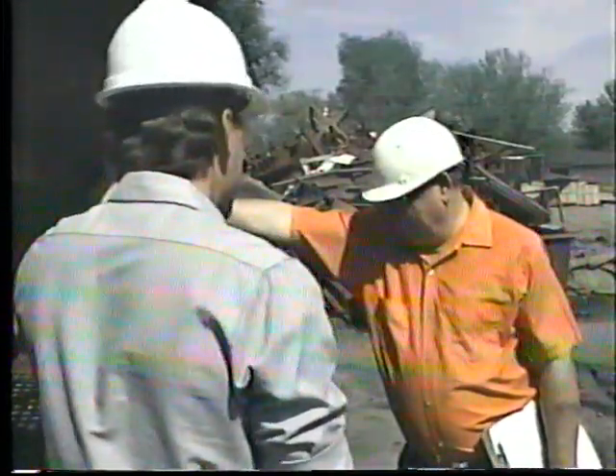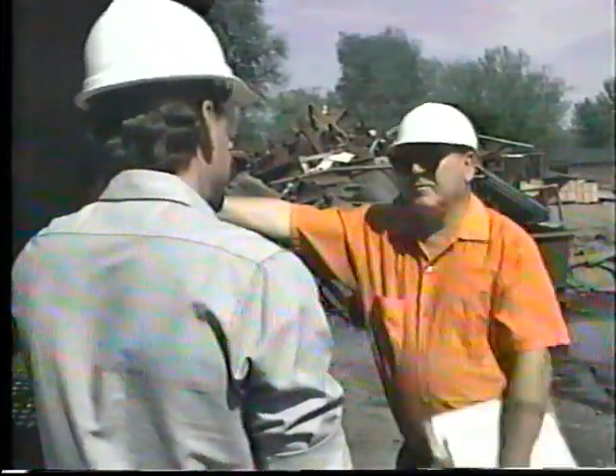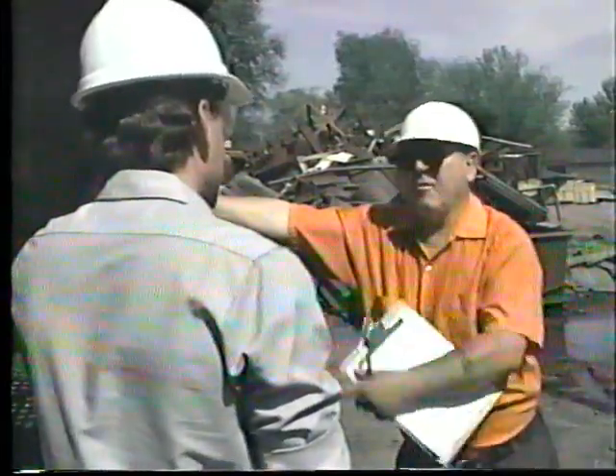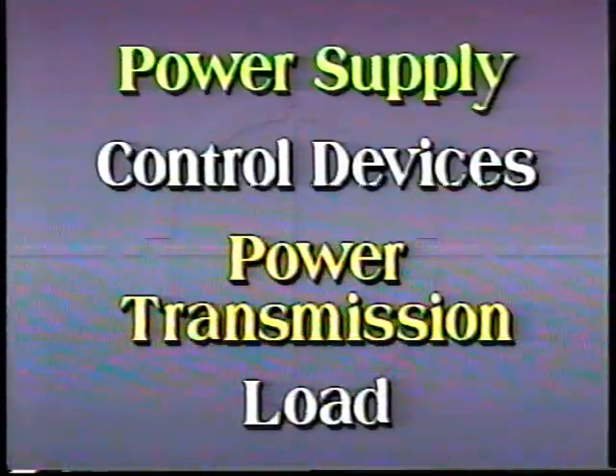It may also be a good idea to ask the operator about recent changes. This could be a process change, a raw materials change, or even a change of suppliers. Often, the operator is the best source of information about unusual machine behavior at the time of the malfunction. When you are faced with very complex systems, your search for symptoms may be more thorough if you can mentally divide a system into categories. Here's a 4-part division that's often helpful.